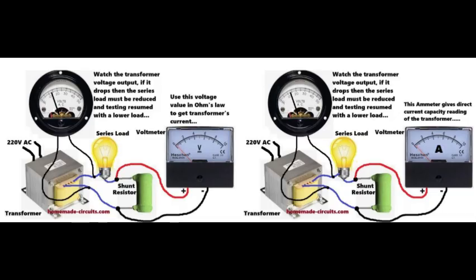Correct and safe method. We always need to test a transformer's max current like this. Connect a proper load, like bulbs or resistors. Put the shunt resistor in series with the load. Connect the ammeter across the shunt. Measure voltage drop across the shunt, calculate current. Slowly increase load. Stop when voltage drops too much or the transformer gets hot. That current is your safe maximum rating.